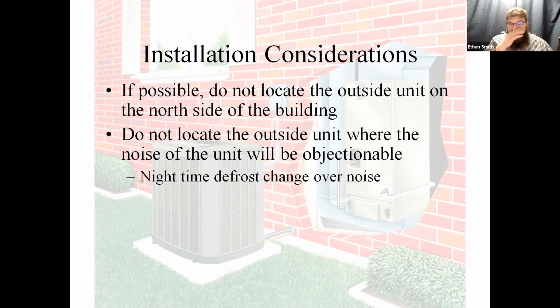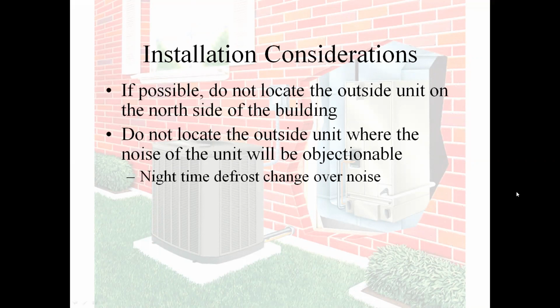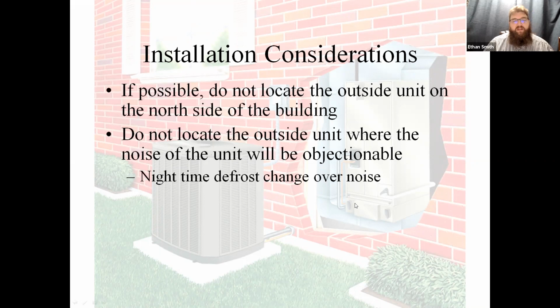I run a heat pump on my house. I've actually got it set up on the southwest corner of my house so that I'm able to take advantage of that warmer ambient temperature during the winter months. It costs me a little bit on my cooling performance, but my system's a little oversized for my house because I do have a variable speed outdoor unit, so I sized it to the heating load rather than the cooling load. But yeah, I would much rather take a longer line set and take a couple hundred BTUs hit on my capacity versus having a noise problem.